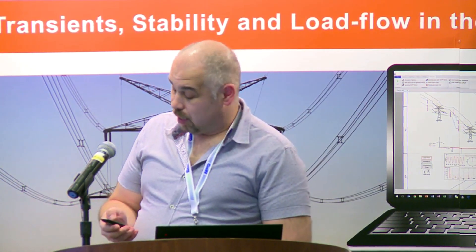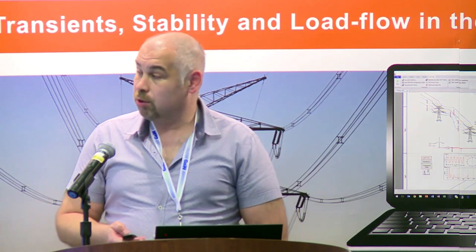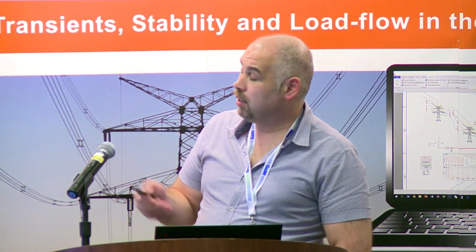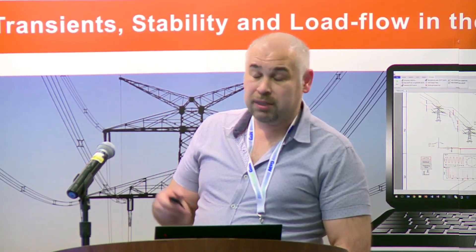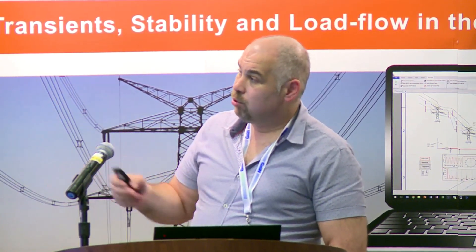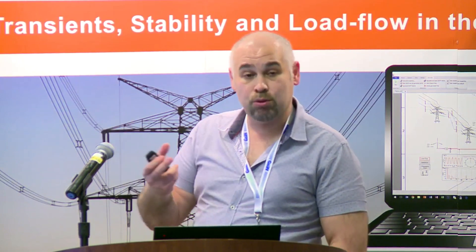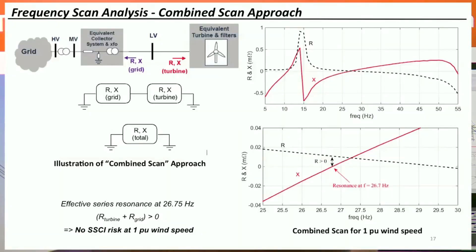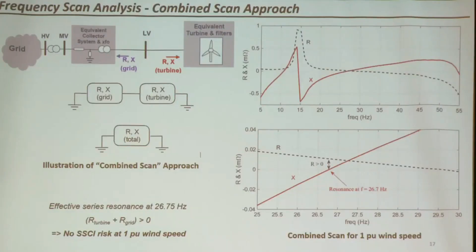This technique was proposed after the ERCOT event. However, the original assessment criteria were not accurate — it recommended performing grid-side and turbine-side frequency scans separately. In reality, both contribute to the resonant conditions, so you must account for both. The grid-side impedance and wind turbine-side impedance must be added together to obtain the combined system characteristics and check for the reactance crossover condition.